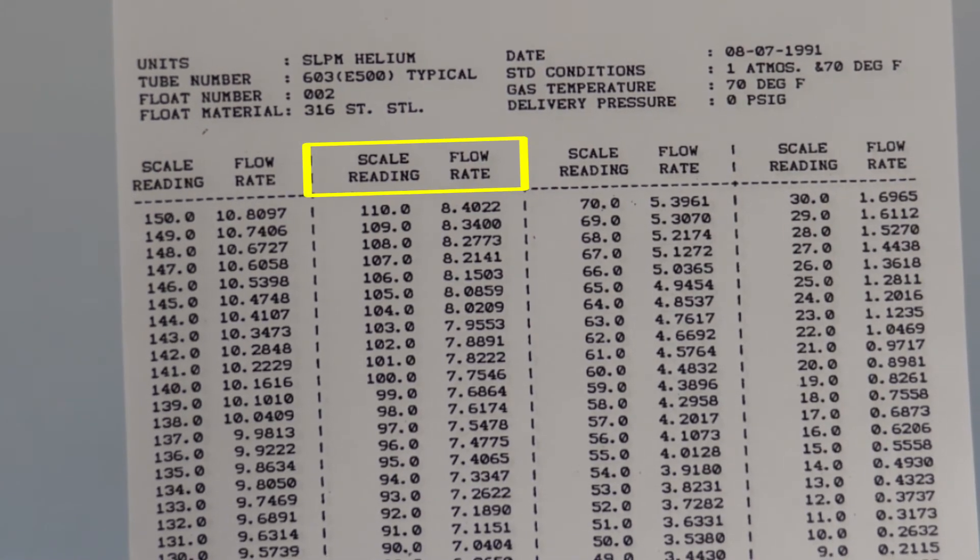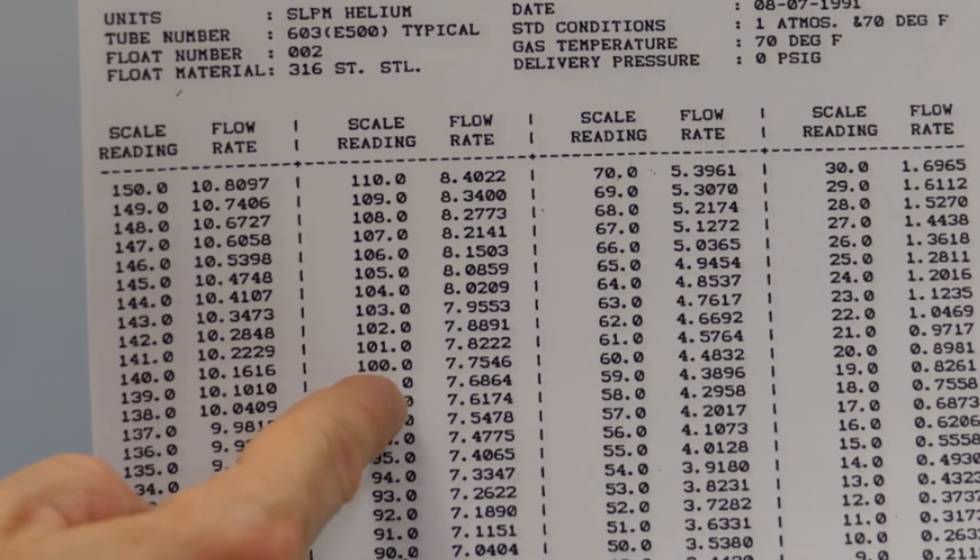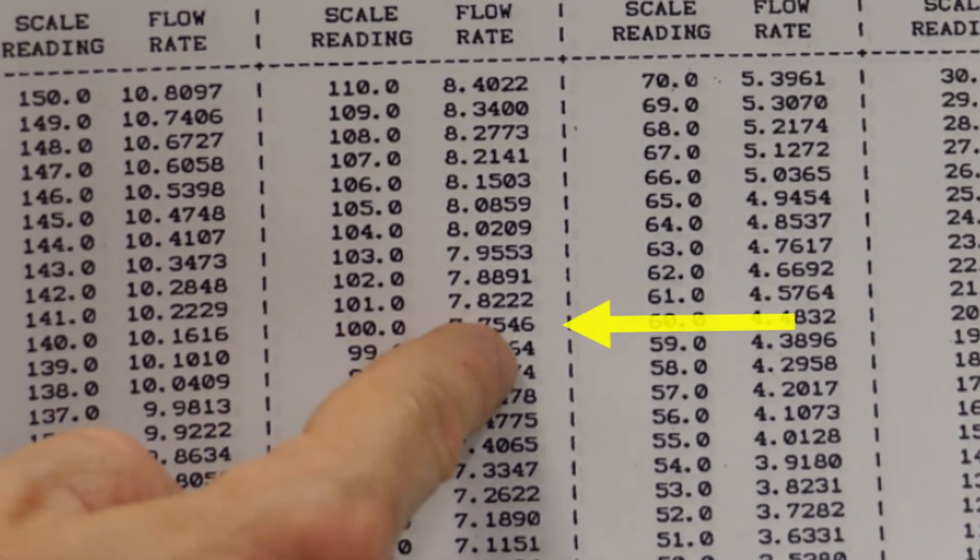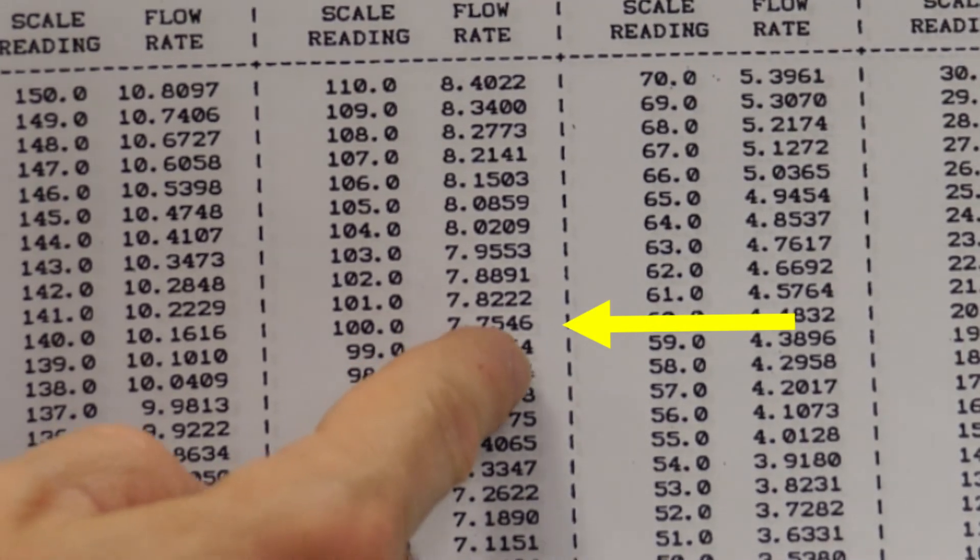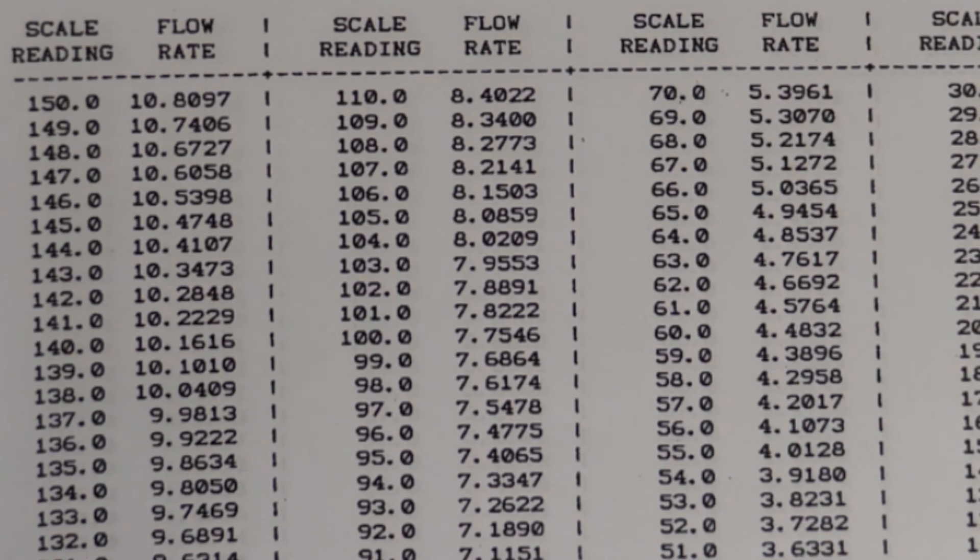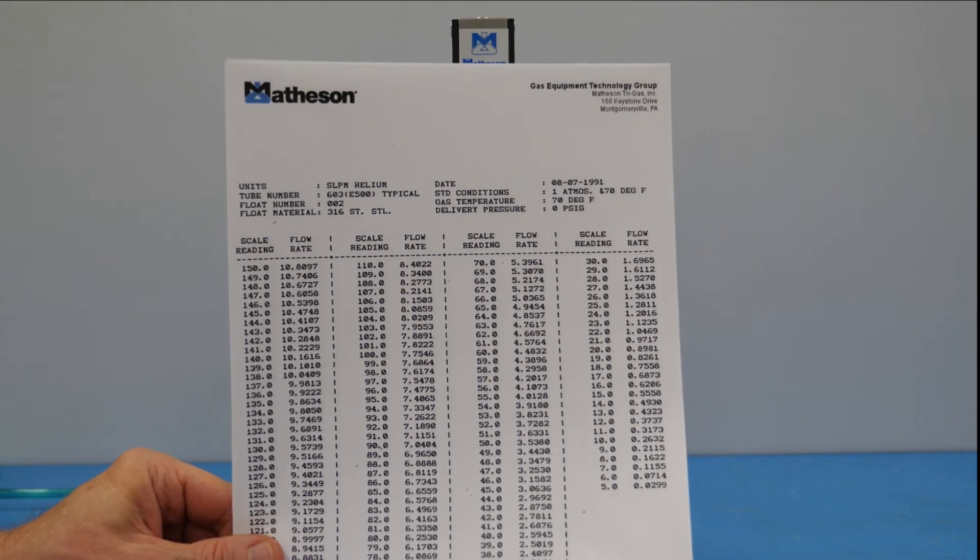So we locate 100 millimeters under the scale reading column, and we shift over to the flow rate, which is 7.7546 standard liters per minute helium. That's essentially how you read and then interpret what your flow rate is.